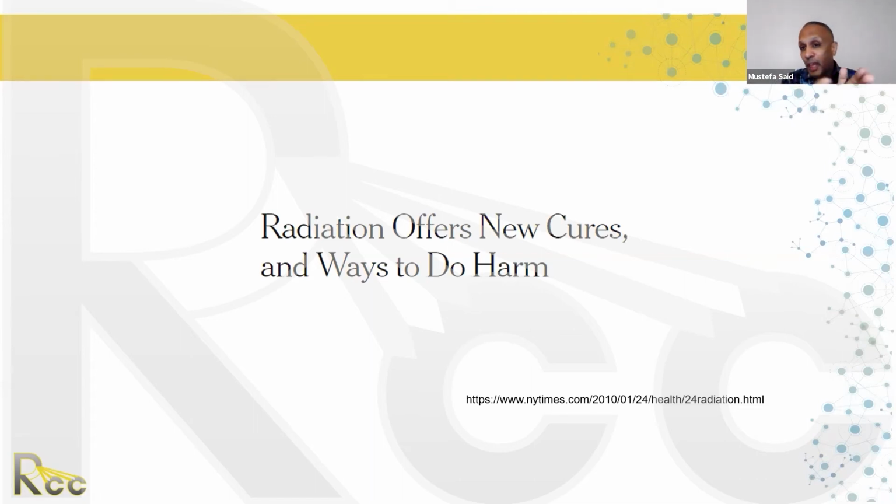Now I'm going to the physics side. Last time I was talking about the radiation therapy side, because the therapists didn't notice the MLC was open. At that time the patient got nauseous, and the therapist was worried. They were using the camera looking at him the whole time, but they failed to look at those MLCs. But today, what caused these MLCs to be open?